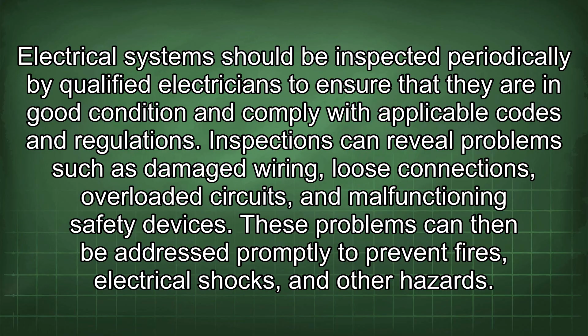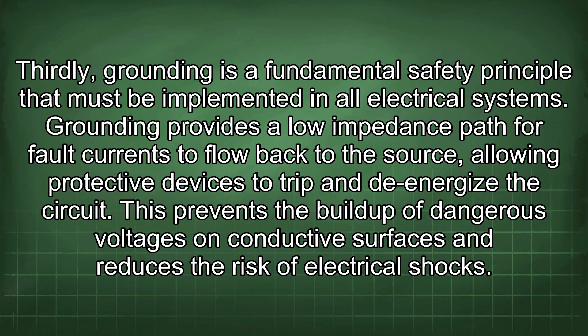Thirdly, grounding is a fundamental safety principle that must be implemented in all electrical systems. Grounding provides a low impedance path for fault currents to flow back to the source, allowing protective devices to trip and de-energize the circuit. This prevents the buildup of dangerous voltages on conductive surfaces and reduces the risk of electrical shocks. Grounding systems must be properly designed, installed, and maintained to ensure their effectiveness.